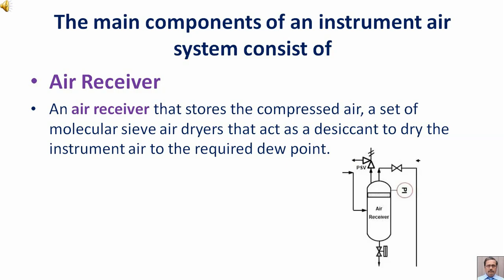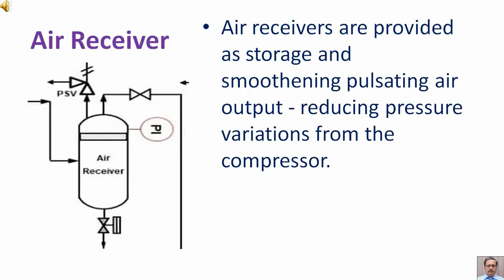Air receiver: An air receiver stores the compressed air. A set of molecular sieve air dryers acts as a desiccant to dry the instrument air to the required dew point. Air receivers are provided for storage and smoothening of pulsating air output, reducing pressure variations from the compressor.